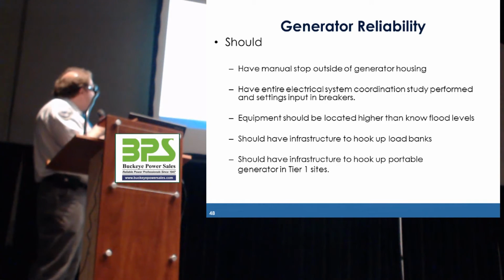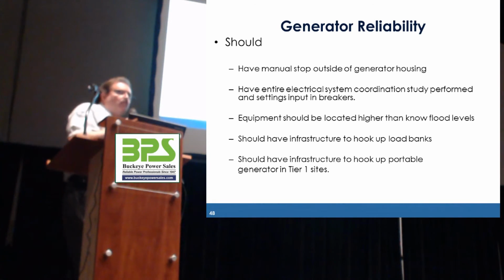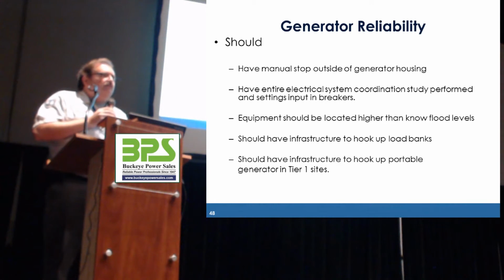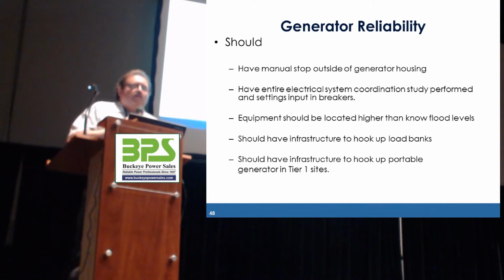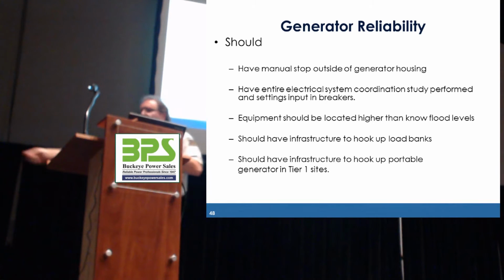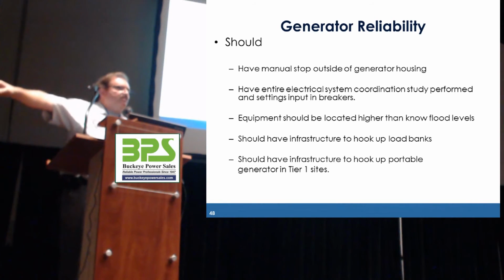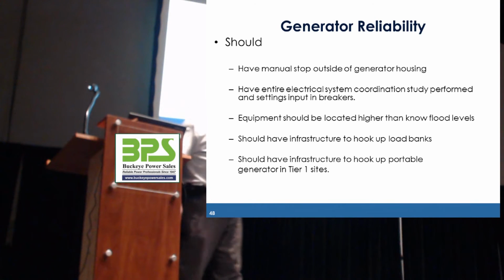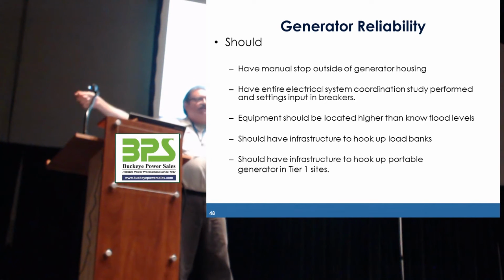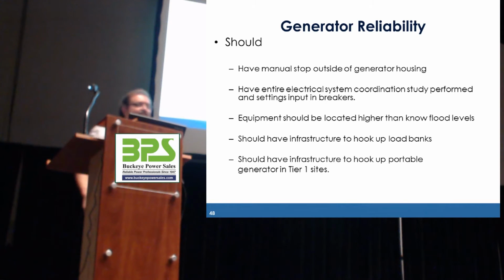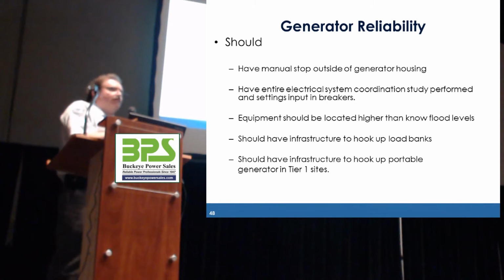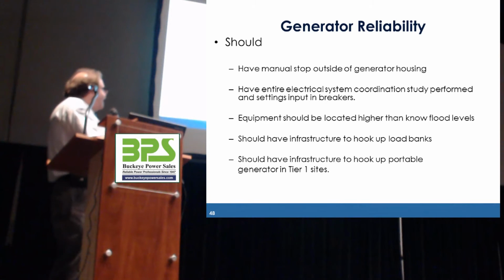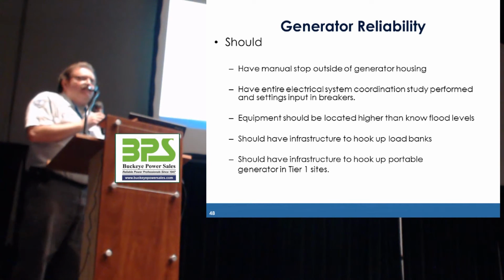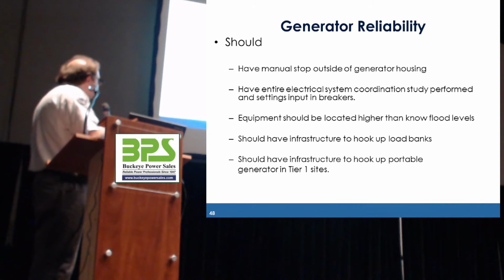Was touched on earlier, the entire electrical system has to have a coordination study done. This is to prevent, and I saw this happen at a hospital, an outpatient place, where the coordination study wasn't done properly. They plugged in a refrigerator into a receptacle. The building main tripped. 1200 amp main tripped because of this little shorted refrigerator. Okay? I don't want to be in that position. So having that coordination study that was talked about during the commissioning is critical.